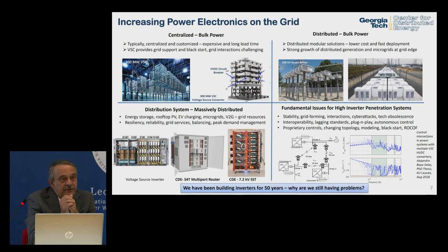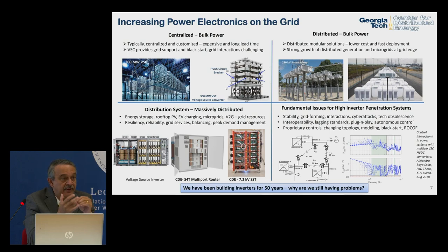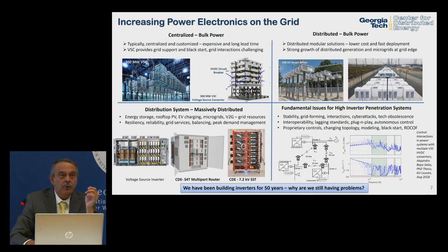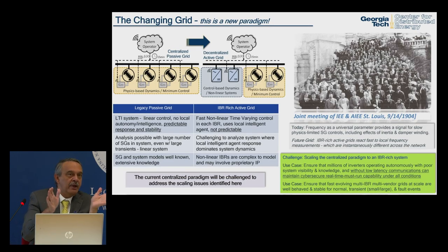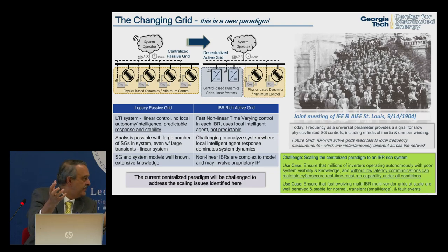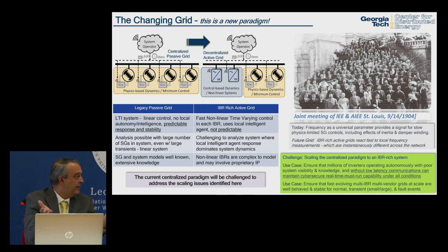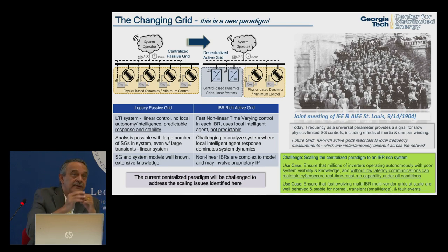We're seeing stability problems in high-inverter-penetration systems. One of the largest grid operators in Europe says they can't even get a system with five inverters to stay stable. The new paradigm: the existing grid is large synchronous generators — passive, mechanical — with a system operator 15 minutes away doing optimization and dispatch. We are moving to a decentralized active grid with intelligent inverters having fast response capability sitting at the edge.